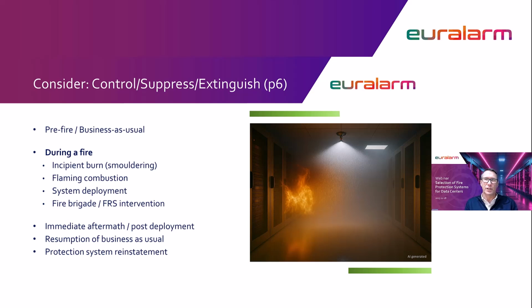The guidance sets this picture and considers each stage of system use, commencing with business as usual. What's it like to live with the system in its quiet, calm, quiescent mode? We then walk through the stages of escalation, though some, as exampled earlier, might not apply. Remember, I asked you to challenge me on the fire growth. The example, diesel doesn't smoulder. You might not have an incipient stage. You can skip that. We take these steps through to conclusion if you have a water-based solution, sprinkler or mist, providing control or suppression that still needs final extinguishment by someone. Normally, that's your fire department, your fire brigade, the fire and rescue service.